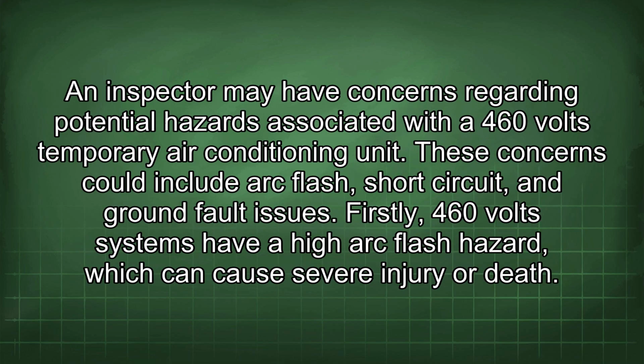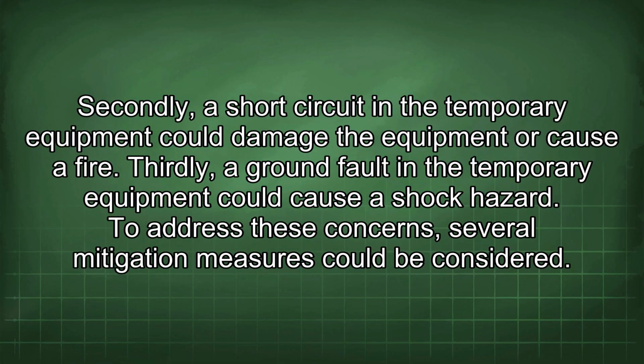An inspector may have concerns regarding potential hazards associated with a 460 volts temporary air conditioning unit. These concerns could include arc flash, short circuit, and ground fault issues. Firstly, 460 volt systems have a high arc flash hazard which can cause severe injury or death. Secondly, a short circuit in the temporary equipment could damage the equipment or cause a fire. Thirdly, a ground fault in the temporary equipment could cause a shock hazard.